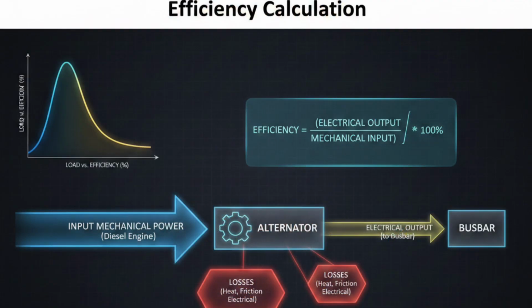You can see from the curve that efficiency is highest near rated load, which is why shipboard diesel generators are normally operated between 60 and 80% loading. Running too lightly loaded or heavily overloaded reduces efficiency and increases wear. Engineers use these curves to plan generator starting sequences, load sharing, and fuel economy strategies.